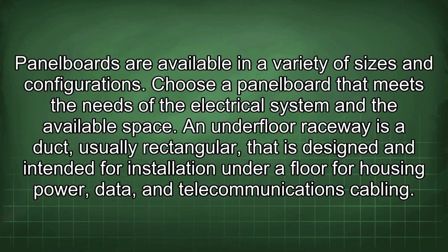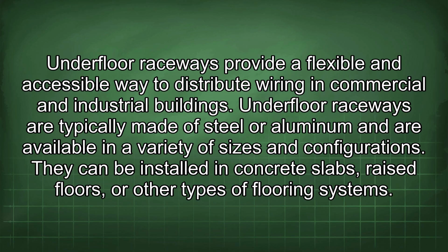An underfloor raceway is a duct, usually rectangular, that is designed and intended for installation underfloor for housing power, data, and telecommunications cabling. Underfloor raceways provide a flexible and accessible way to distribute wiring in commercial and industrial buildings. Underfloor raceways are typically made of steel or aluminum and are available in a variety of sizes and configurations. They can be installed in concrete slabs, raised floors, or other types of flooring systems.